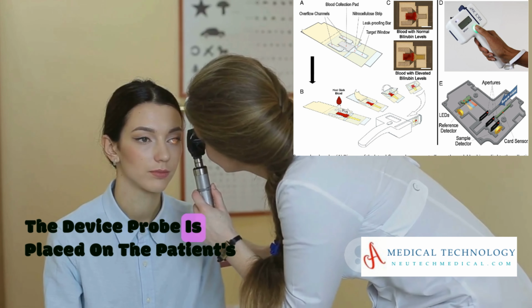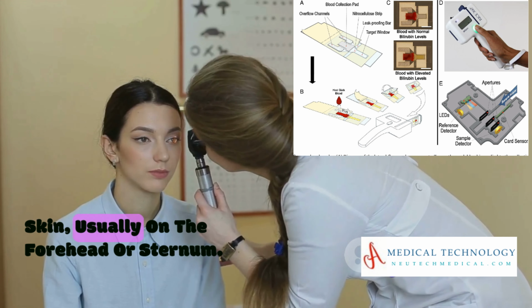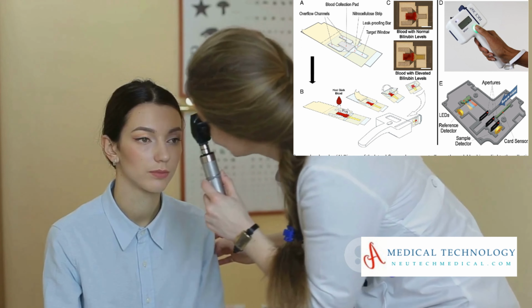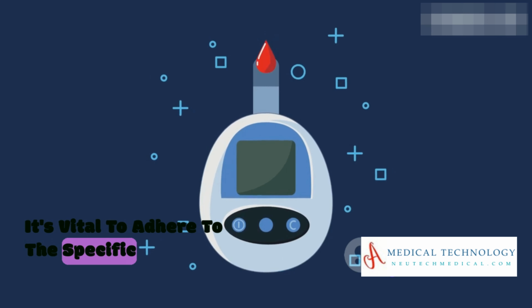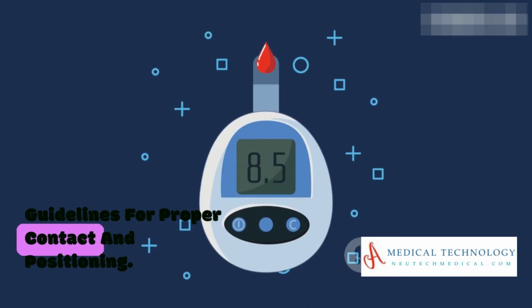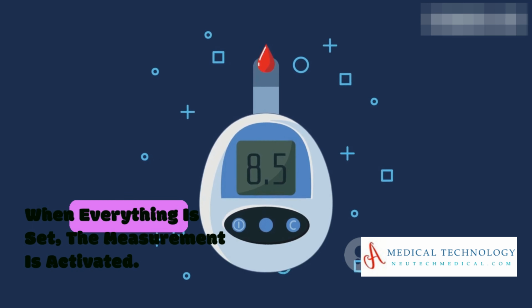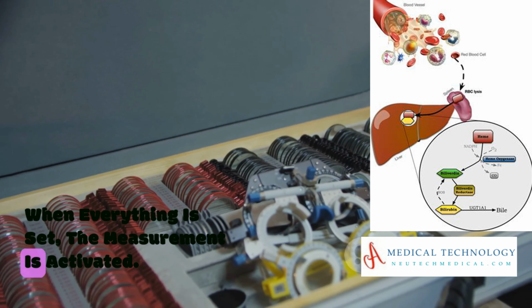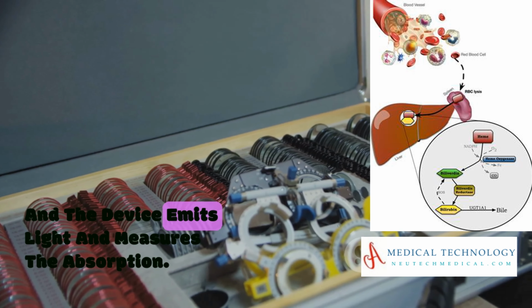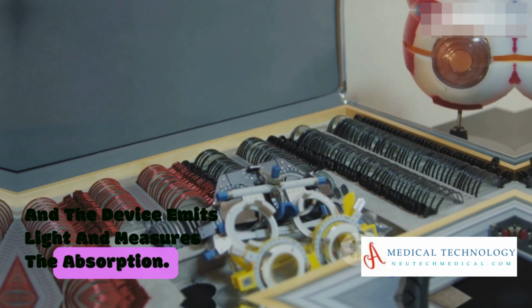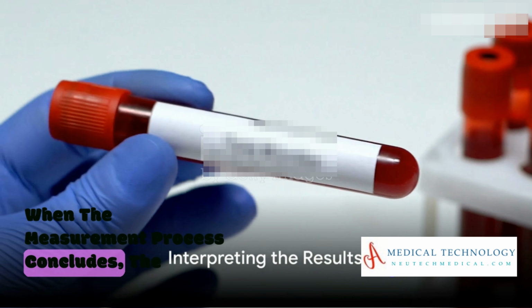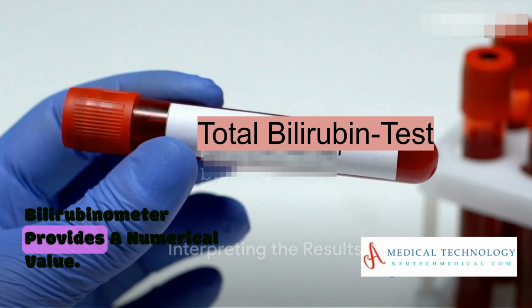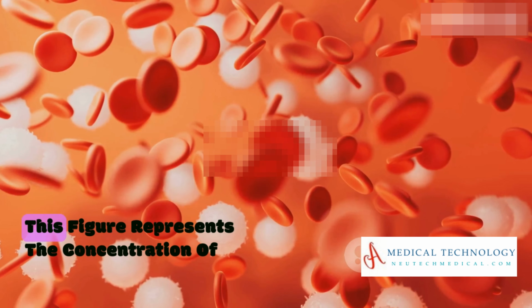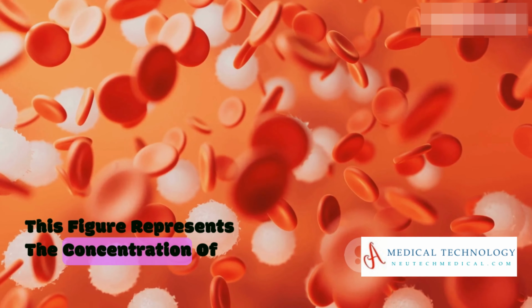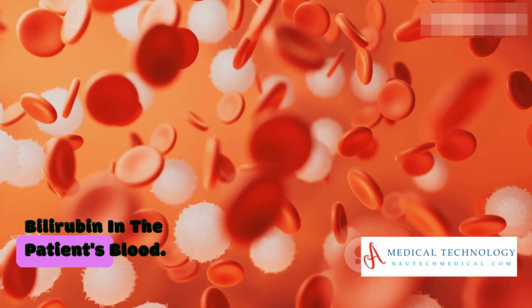The device probe is placed on the patient's skin, usually on the forehead or sternum. It's vital to adhere to the specific guidelines for proper contact and positioning. When everything is set, the measurement is activated and the device emits light and measures the absorption. When the measurement process concludes, the bilirubinometer provides a numerical value. This figure represents the concentration of bilirubin in the patient's blood.